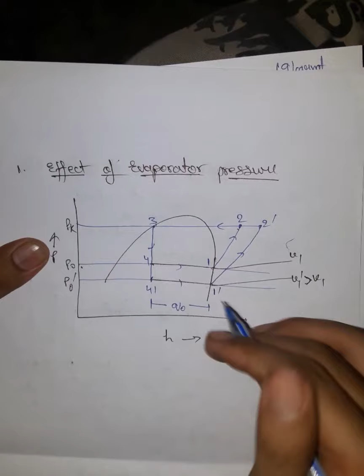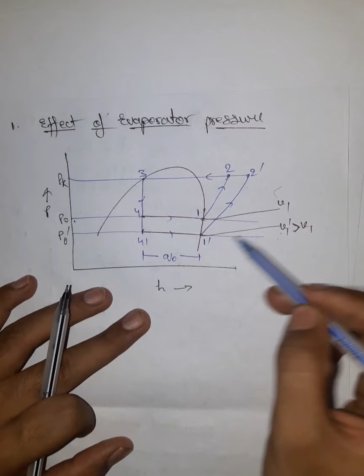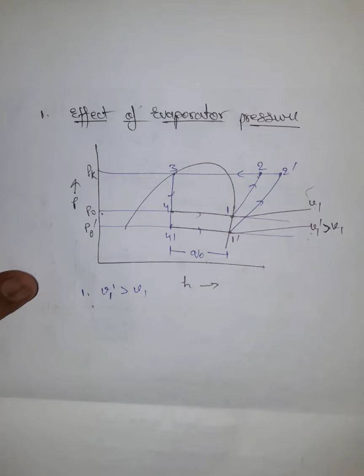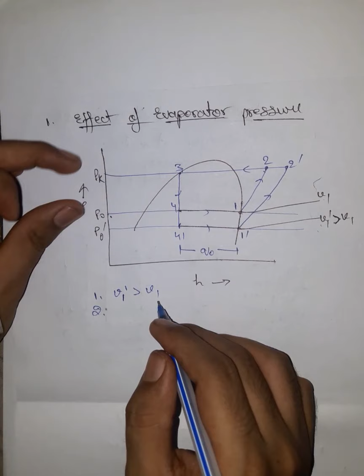The first change that we can see here is in the specific volume. At point 1, the specific volume is v1, which is smaller than the specific volume at point 1 dash, v1 dash. It can be inferred from the diagram, as we know that in the p-h diagram the specific volume increases going downwards. So v1 dash is greater than v1, that means specific volume increases. Second is the pressure ratio. Earlier it was P2 over P1, and it is less than P2 dash over P1 dash. P2 dash is the same as P2, but you can see from the diagram that this difference is larger than this difference, so the pressure ratio has increased by lowering the evaporator pressure.